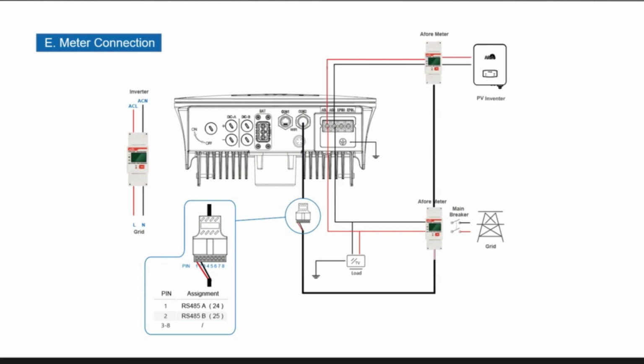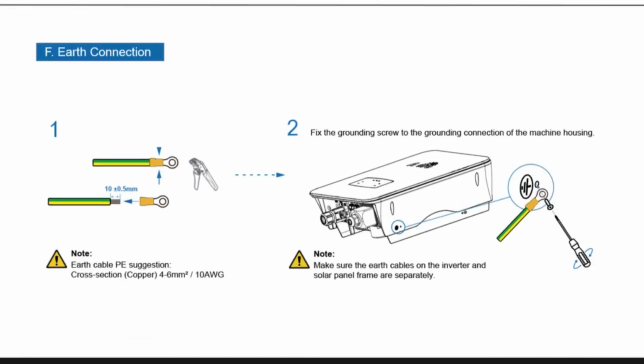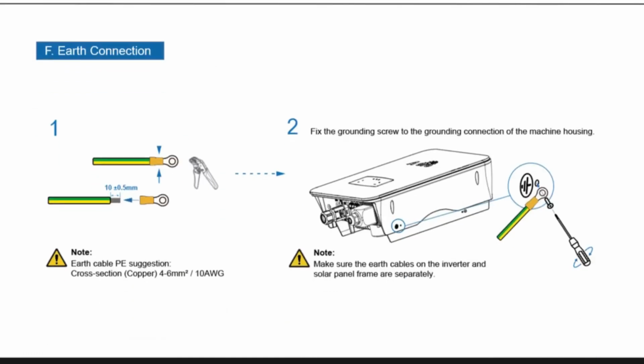Now unfortunately, I'm telling you all of this information and I've just found out the next generation of single phase hybrid is on its way, where we'll actually have 3 COM ports in the bottom of the inverter. COM1 is for a series connection, COM2 for the RS485 is for the meter and the CT, and COM3 is for the battery. So in future, you won't actually need to go through the way I'm going through at the moment. You can actually plug an RS485 plug into each one of the connections that you actually need, and you don't need a green plug, so plug and play on the next generation of hybrid inverters that are coming in.